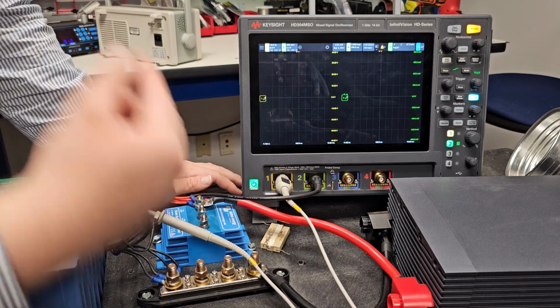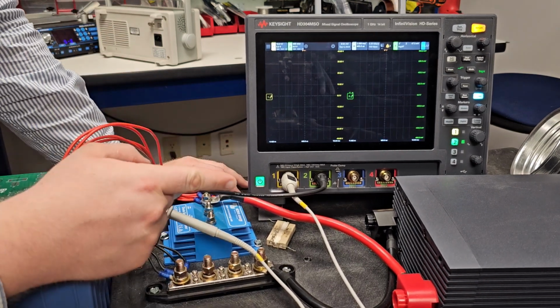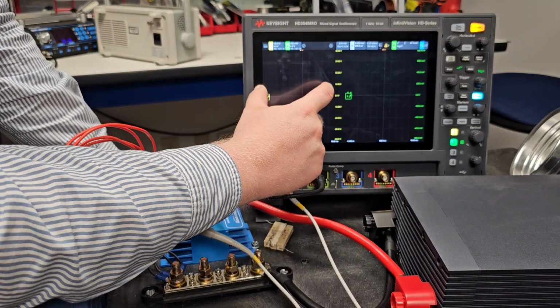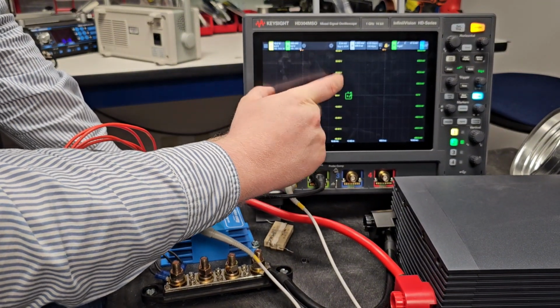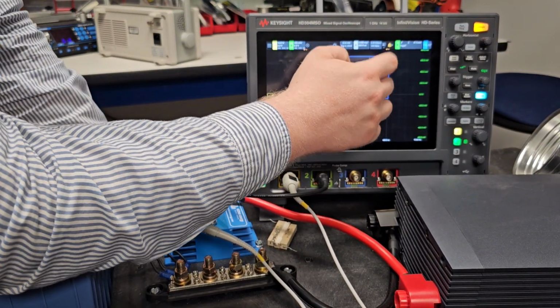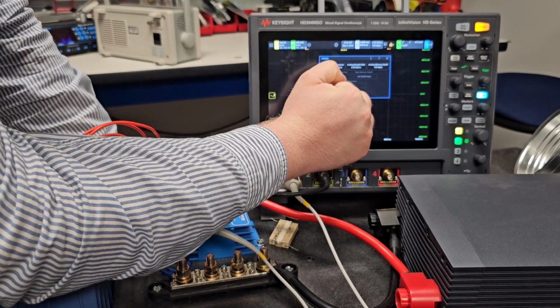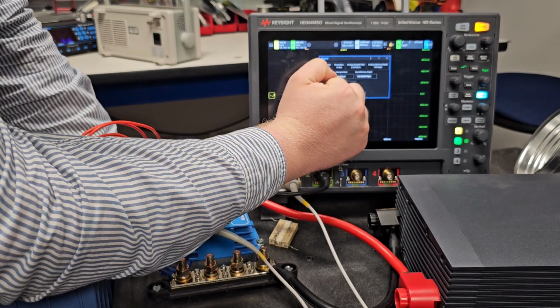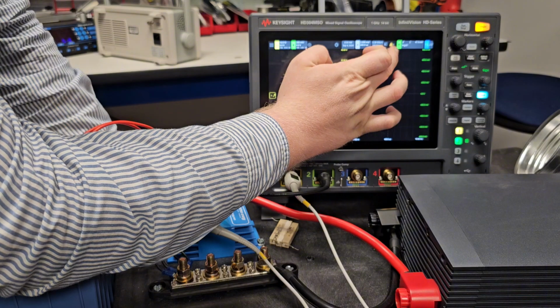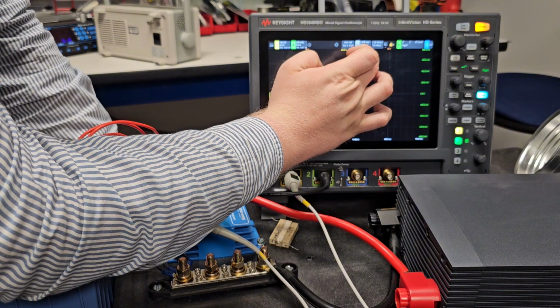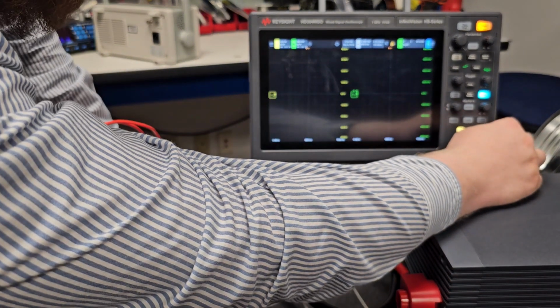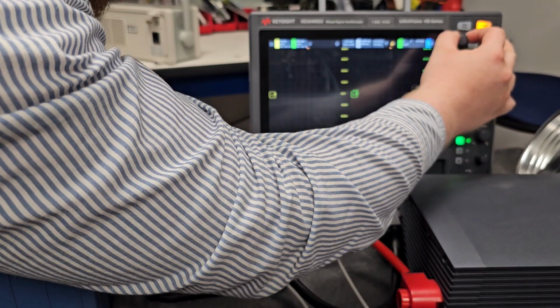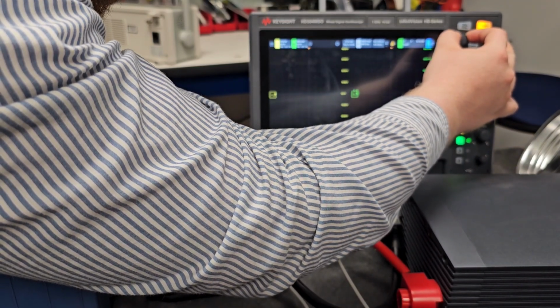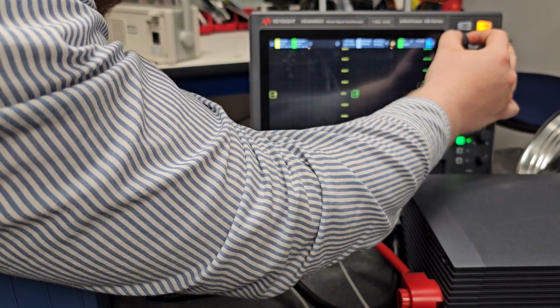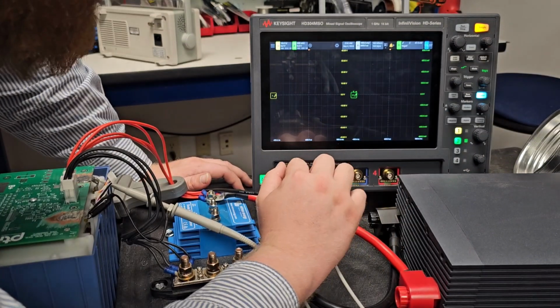So for this test, I noticed before that I kind of maxed out my horizontal range by doing the memory the way I did. So what I'm going to do is put this not in manual mode, but in auto mode. And then I'm going to change my horizontal to, let's say, 500 milliseconds. That's interesting.